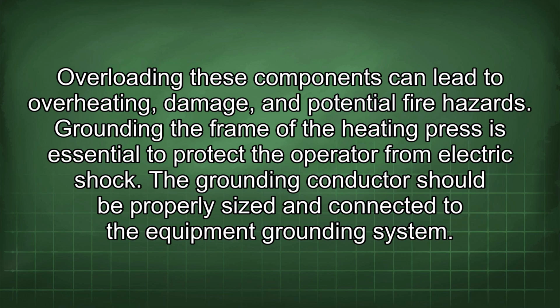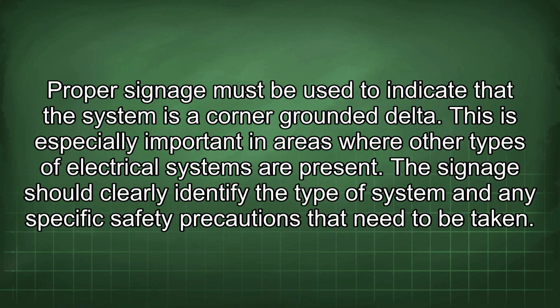Grounding the frame of the heating press is essential to protect the operator from electric shock. The grounding conductor should be properly sized and connected to the equipment grounding system. Proper signage must be used to indicate that the system is a corner-grounded delta. This is especially important in areas where other types of electrical systems are present. The signage should clearly identify the type of system and any specific safety precautions that need to be taken.